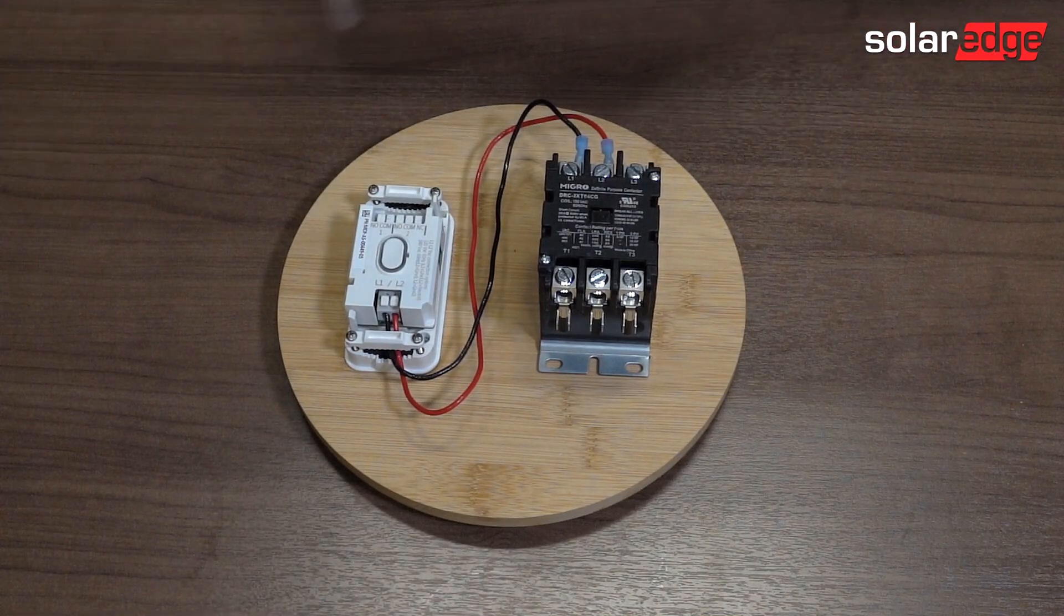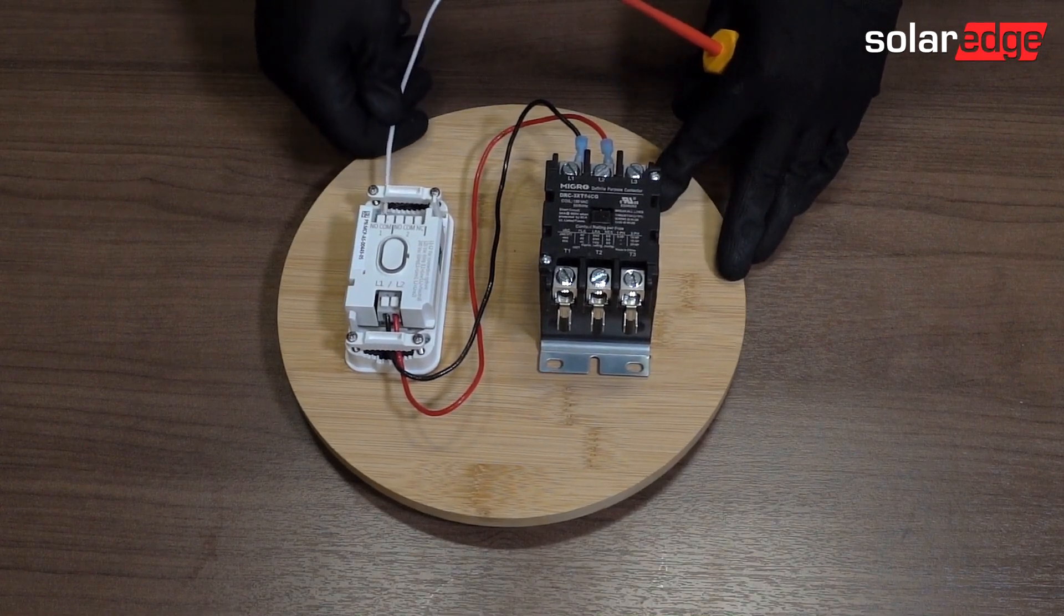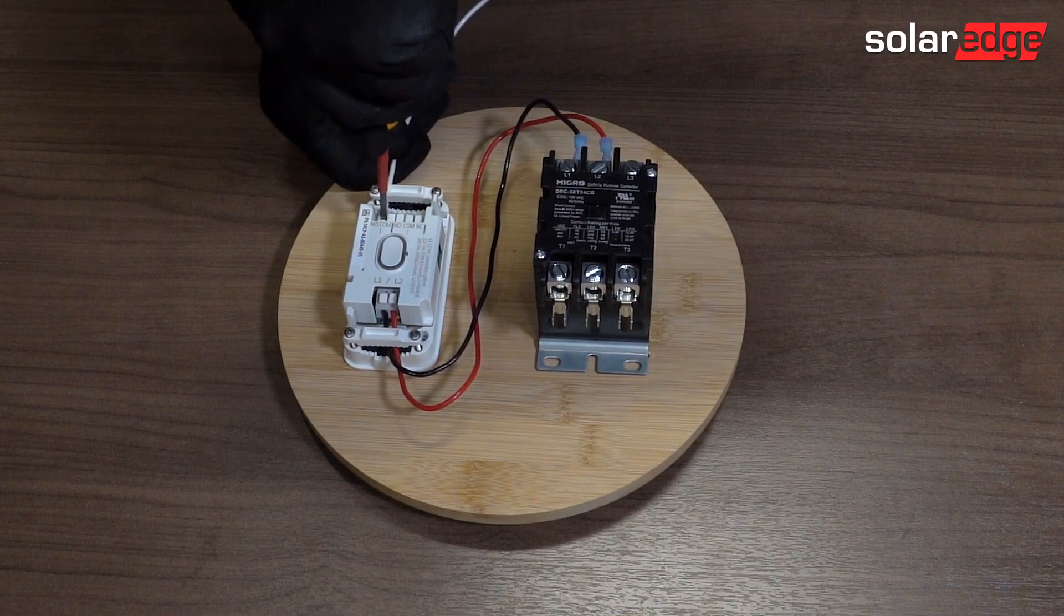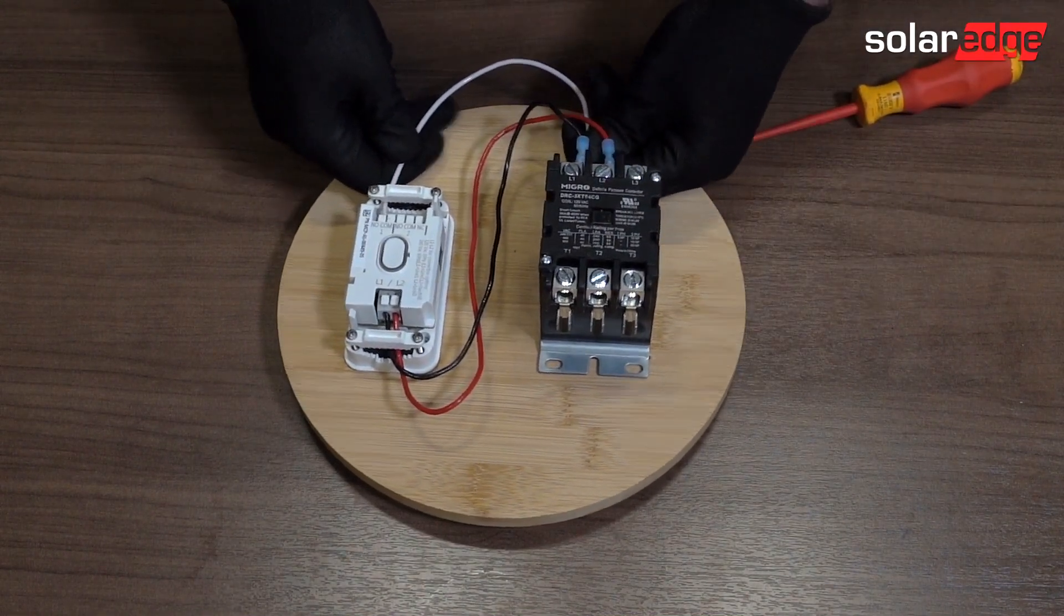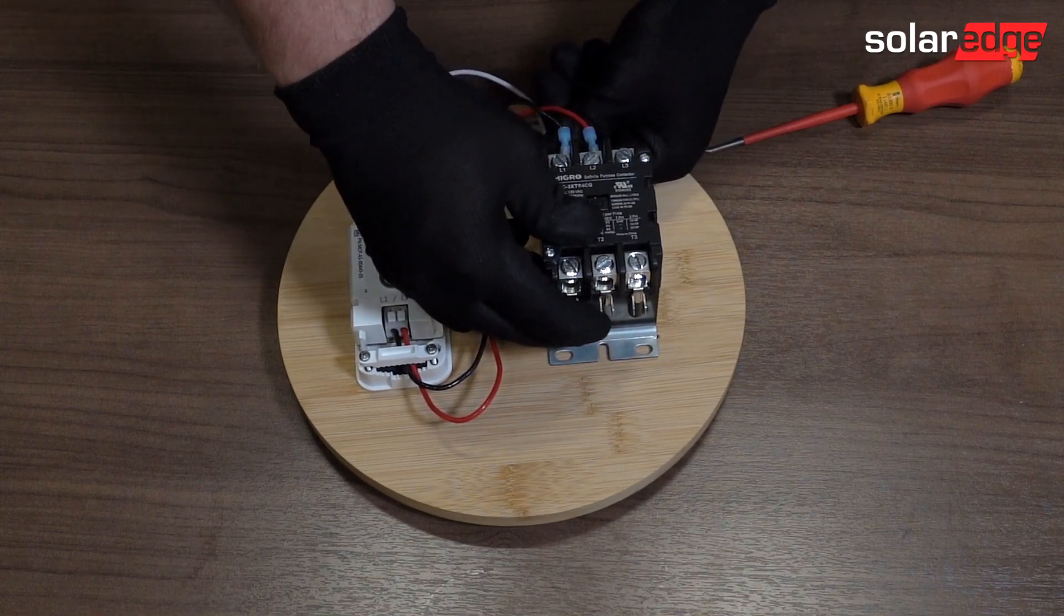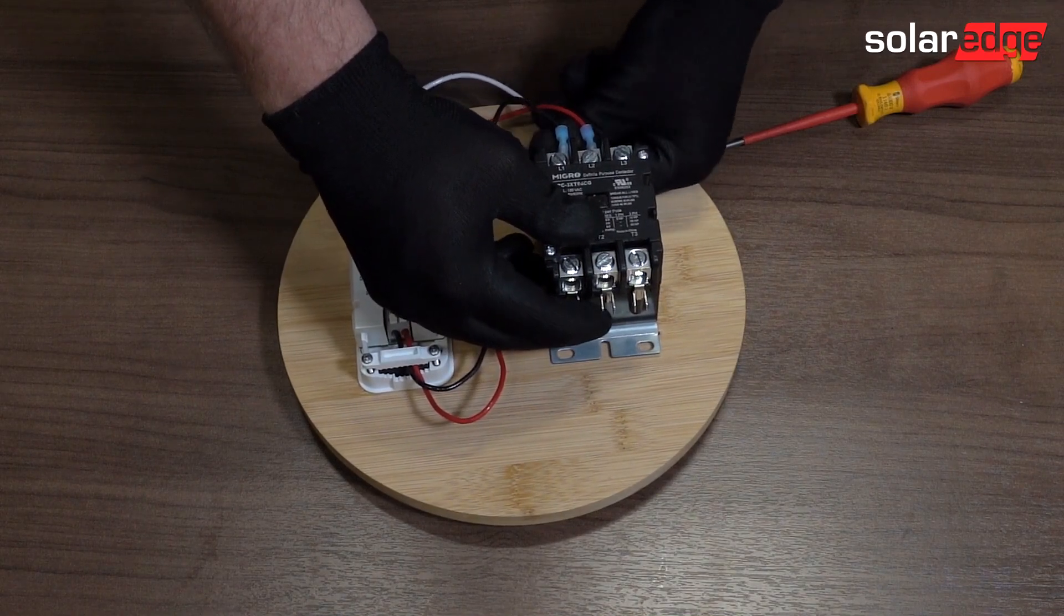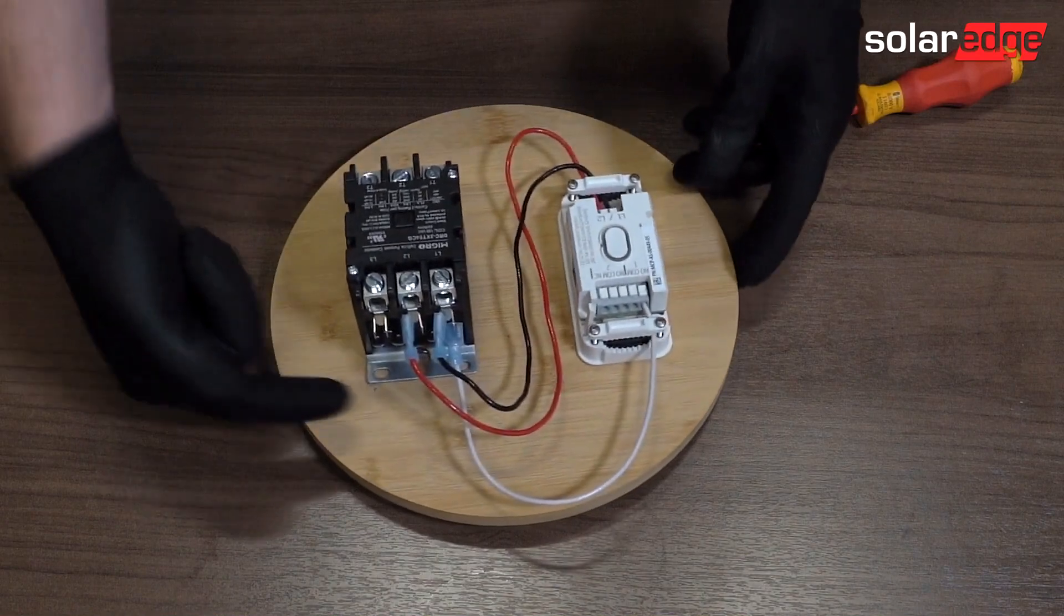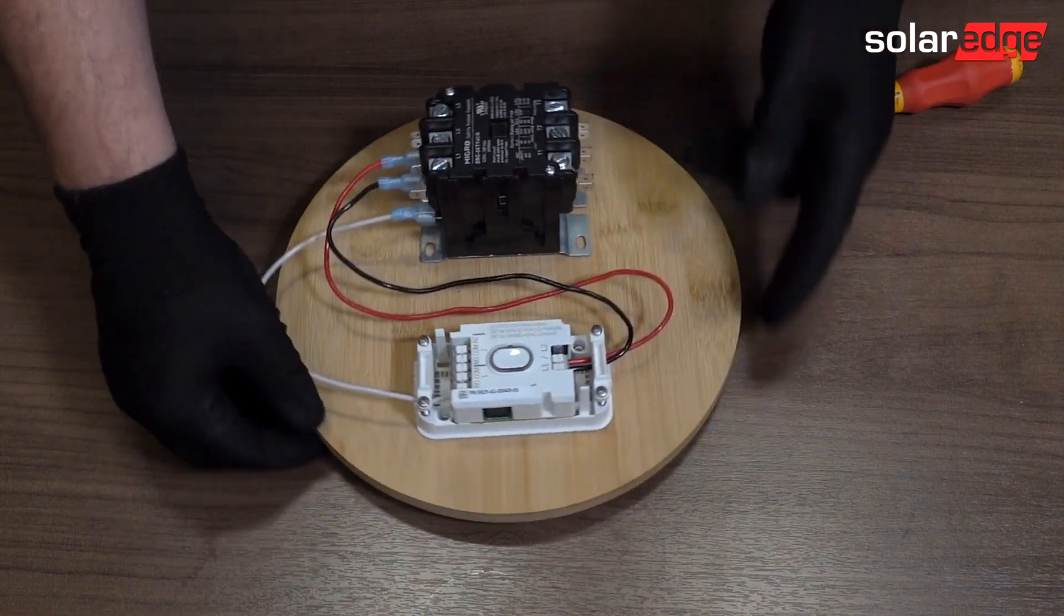So let's do our normally open first. I'm going to use a white wire because this is a 120 volt coil, and I'm going to run a neutral to my coil. We're going to land here at the bottom into the A1 position. Come on. I'm going to give you a little spin so you can see. You can see that's landed on the bottom here on the A1 position, the coil.